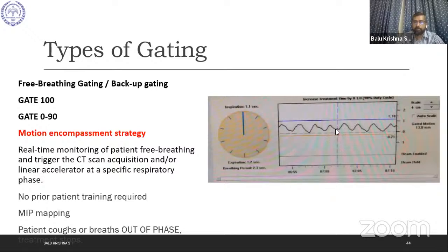And once that is done, when the patient goes for treatment, the same gate is employed, the same respiratory monitoring is employed. If the patient breathes out of phase, that is generally when they cough, or if they have some kind of respiratory issue, they hyperventilate, and it goes beyond this, the beam automatically stops. Within this window, we have already accounted for that error by generating the MIP. So this kind of gating is called free breathing gating or backup gating.